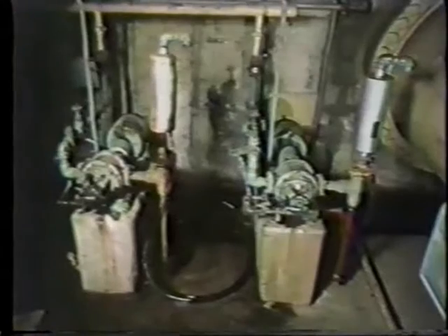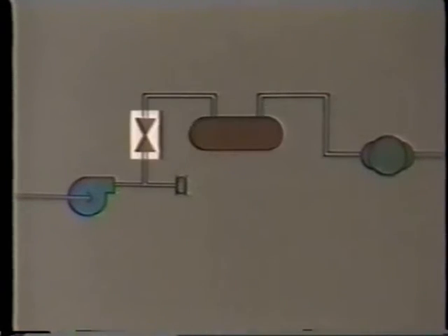For these pumps, a priming system will be provided. So, let's take a minute and talk about one type of priming system. This system consists of a vacuum pump, a priming tank, and a priming valve. The vacuum pump removes air from the priming tank. When air is removed from the priming tank, a vacuum is formed in the tank and in the piping of the priming system. The priming valve is located between the priming tank and each circulating water pump. The function of a priming valve is to open should air enter the pump for any reason. As long as the pump is filled with water, the priming valve remains closed.